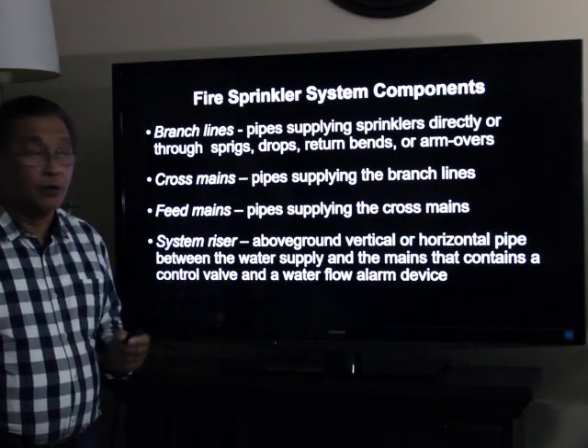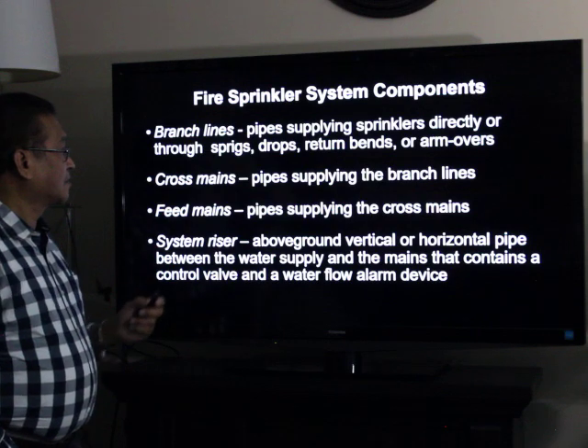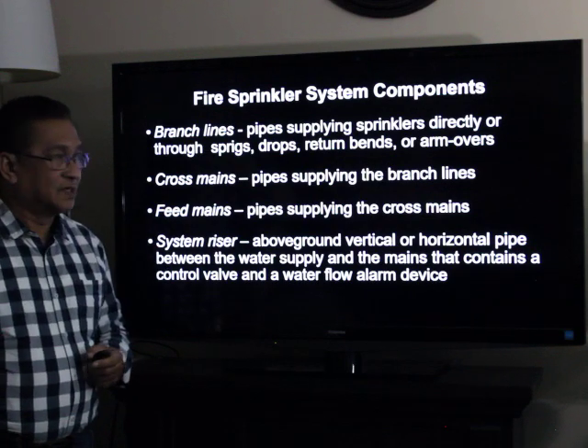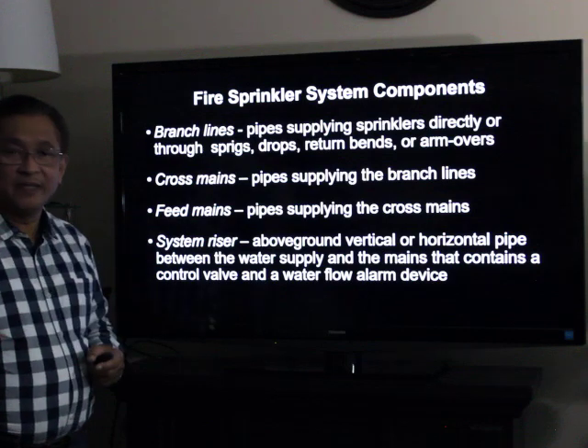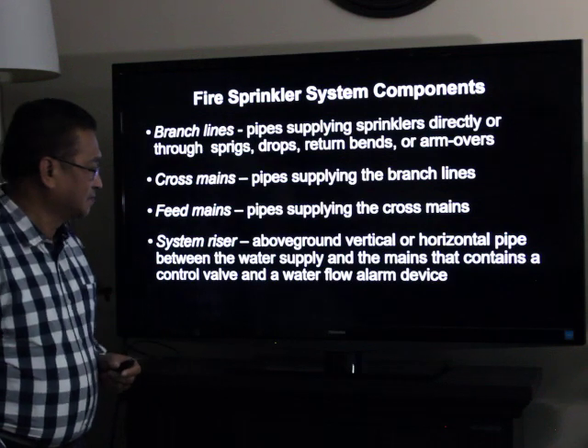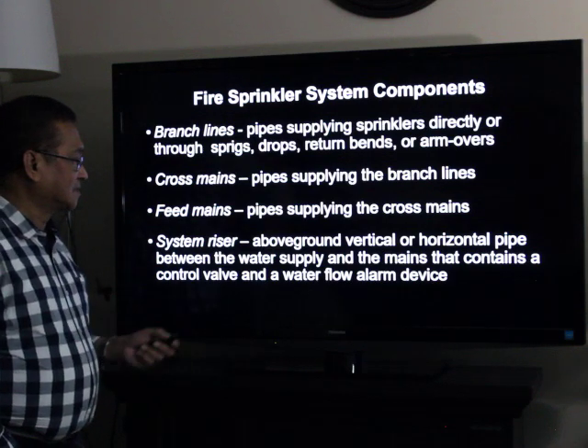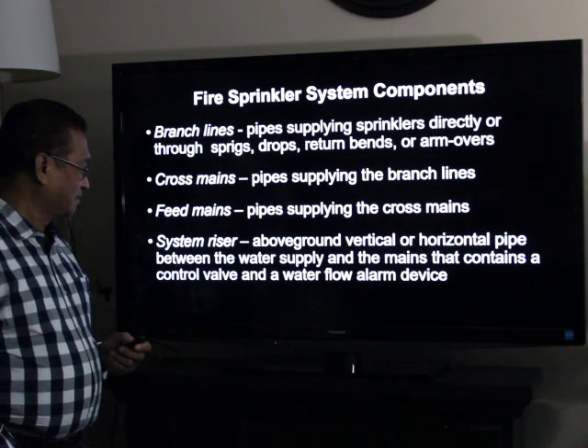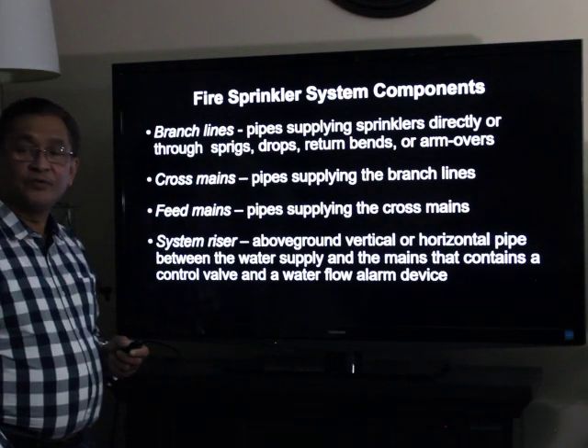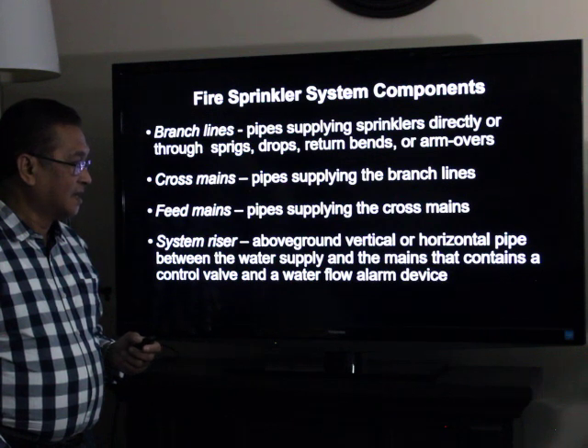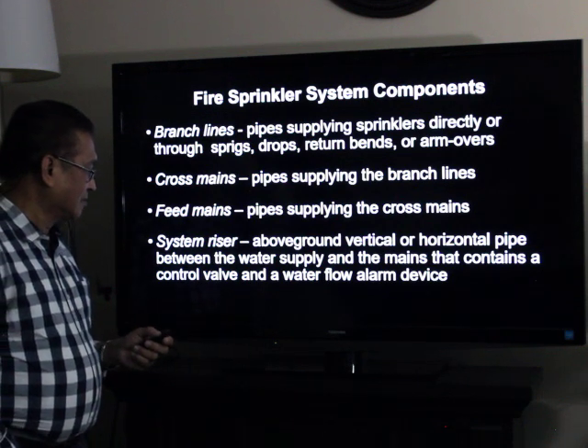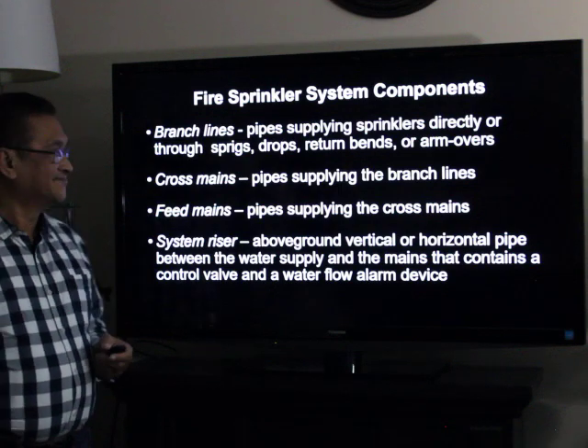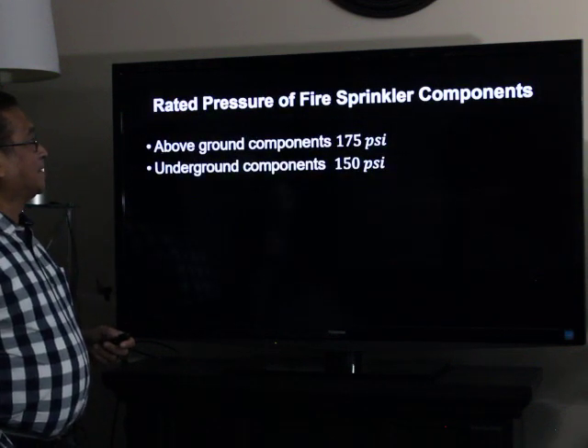Cross mains are the pipes supplying the branch lines. Feed mains are the pipes supplying the cross mains. The system riser is the above-ground vertical or horizontal pipe between the water supply and the mains that contains a control valve and a water flow alarm device.